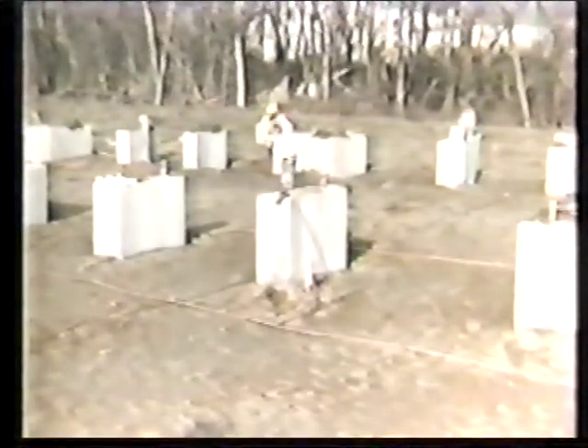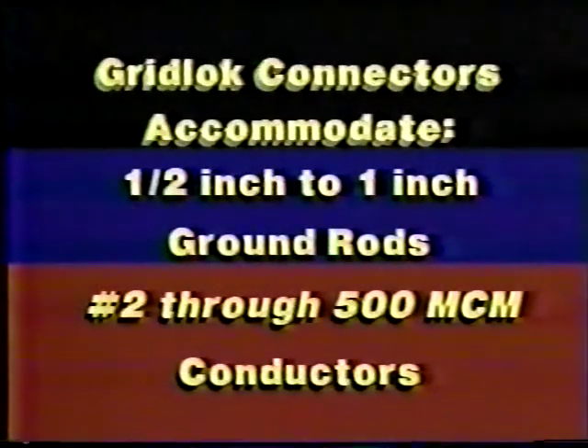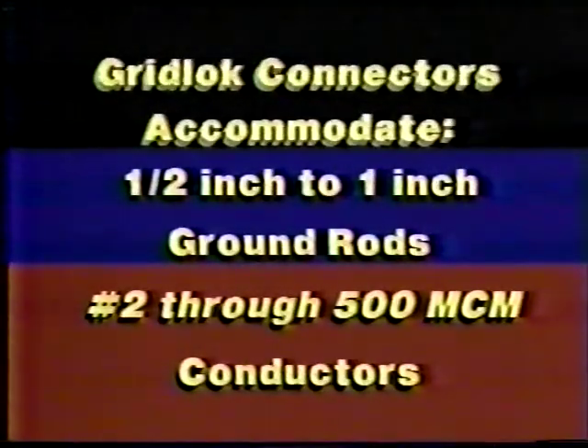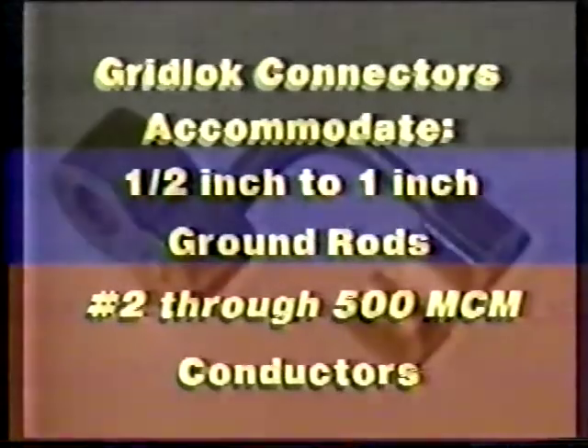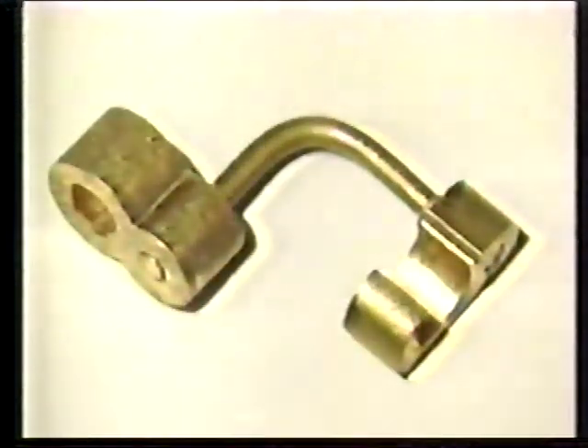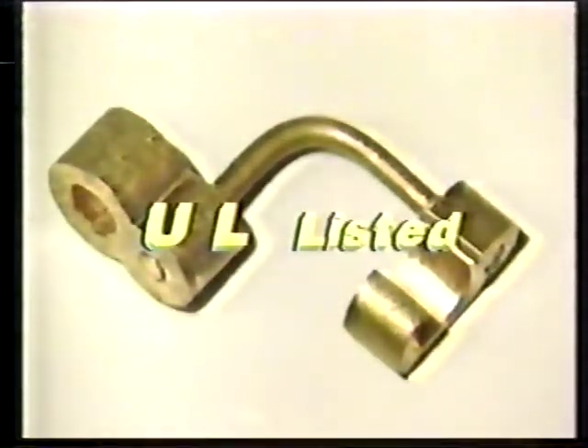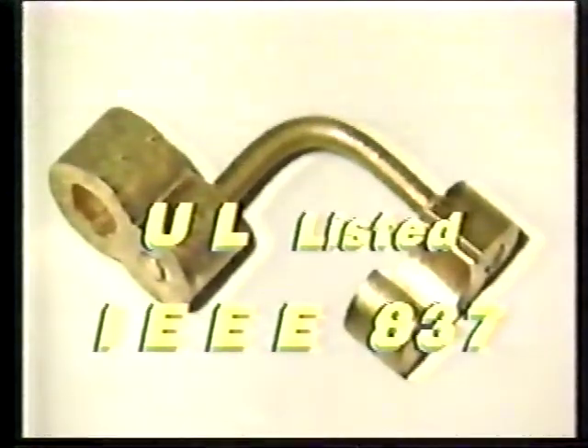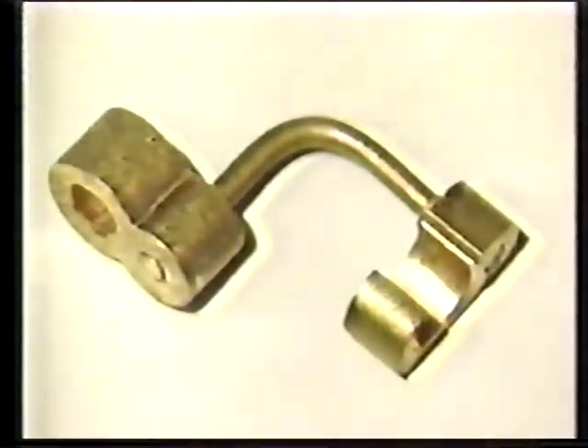For effective operation, the ground grid should be connected to ground rods which have been driven into the earth. To handle this requirement, Burndy features a full range of Gridlok connectors which accommodate ground rod diameters of 1/2 to 1 inch and conductors from number 2 through 500 MCM. As with our cross connectors, Burndy's grid-to-ground rod connectors are UL listed and meet the latest requirements of IEEE 837. They're suitable for use on copper-clad and stainless steel ground rods.